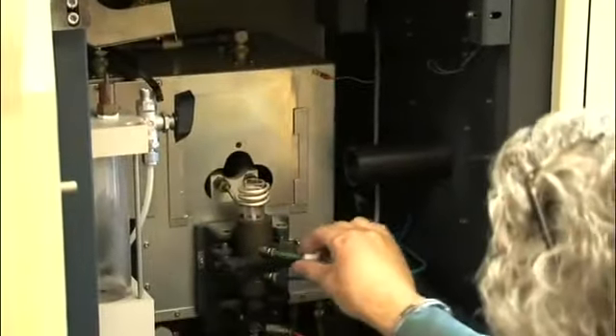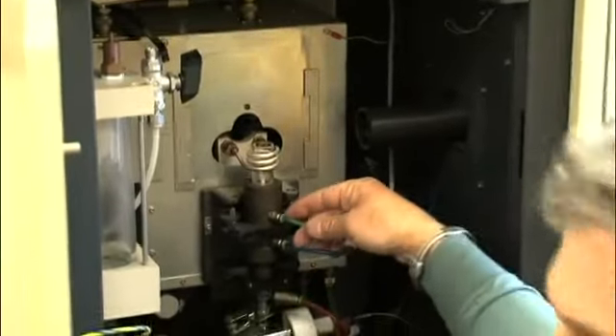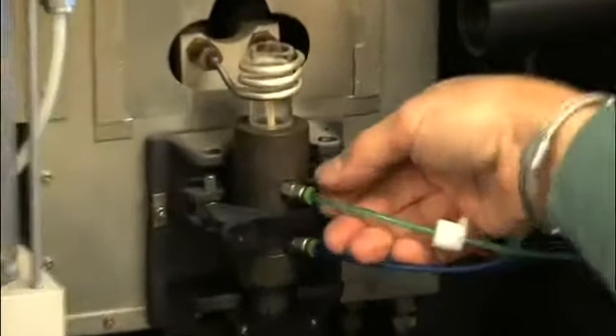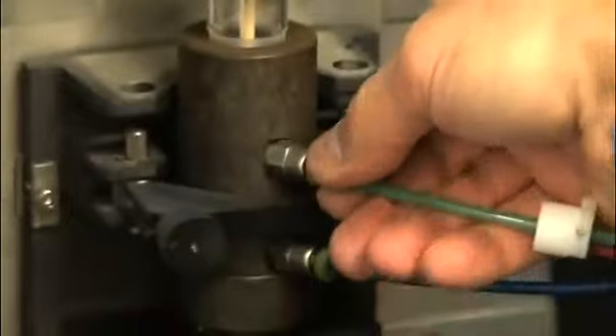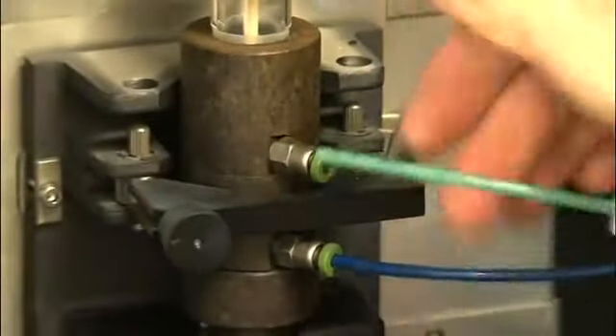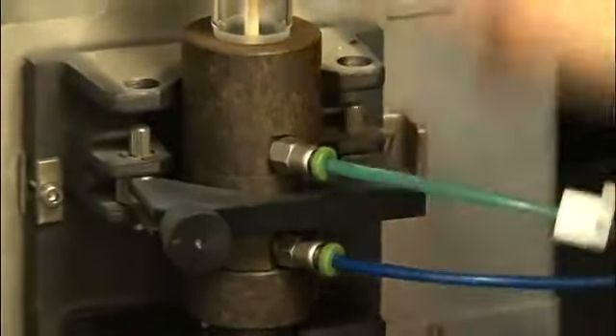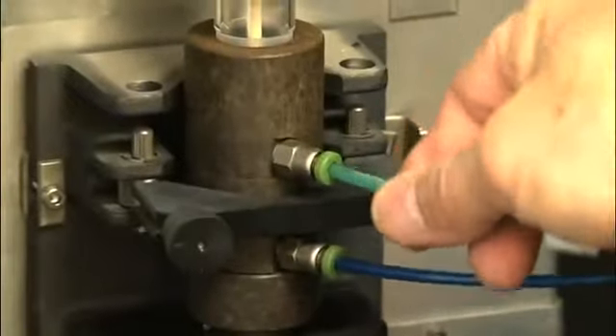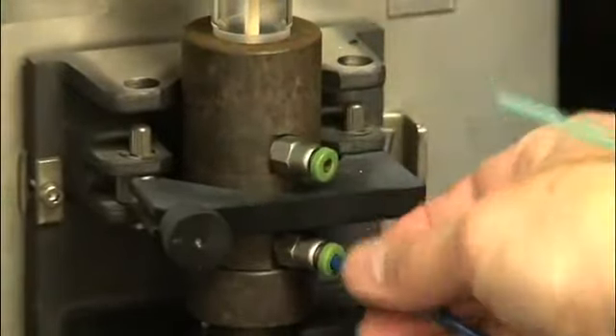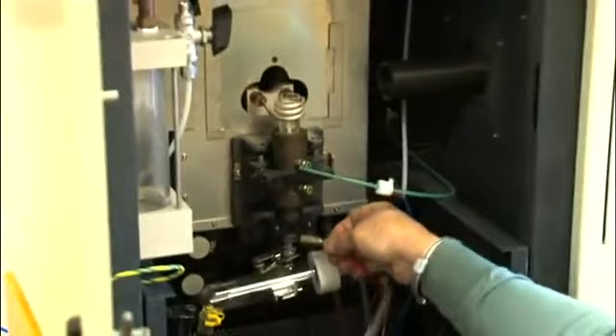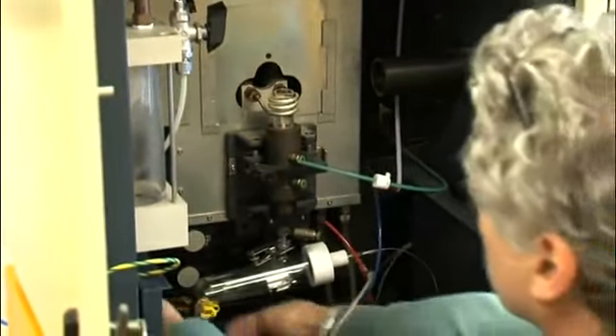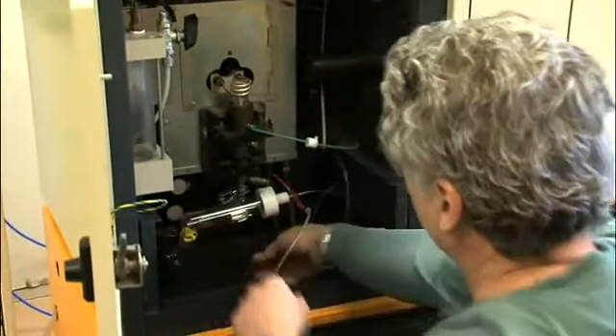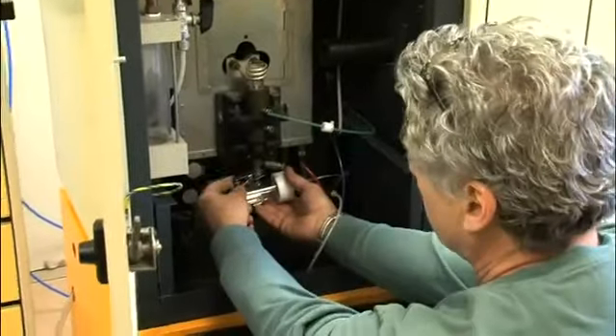Your torch comes out by, these are all quick gas connects. You push on the green ring and you pull on the hose at the same time and it comes out. When you're putting it back in, all you have to do is push it in. It should not come out unless you push on the green ring. Now, let me just see.